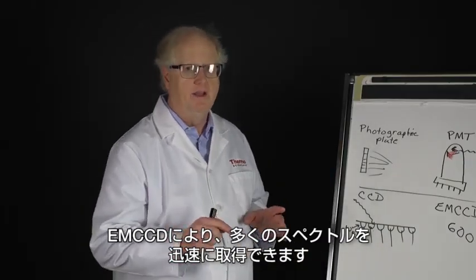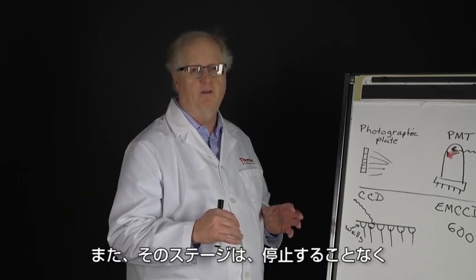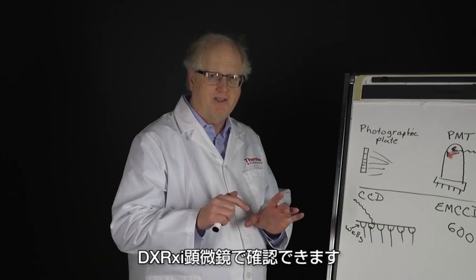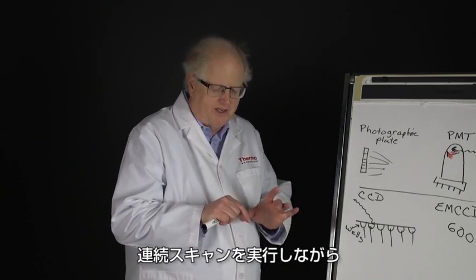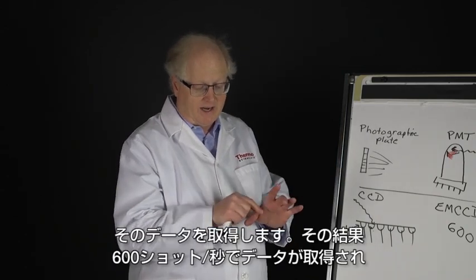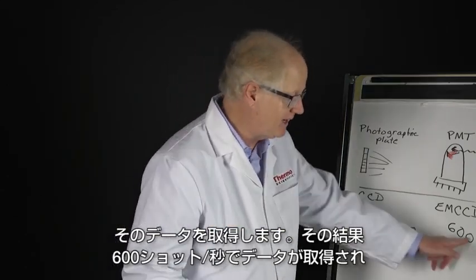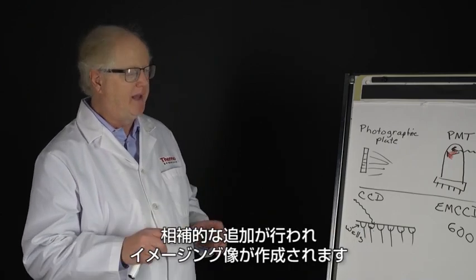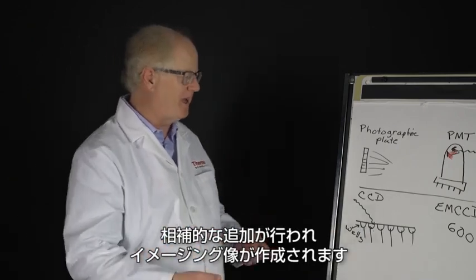It is used to allow you to collect a lot of spectra in a hurry so that you can image. And again referring to the DXR XI microscope, the stage never stops - it actually continuously scans while the EMCCD is clicking away and collecting that data, so that you can collect it at this speed, 600 spectra per second, and then co-add them to build up that image.